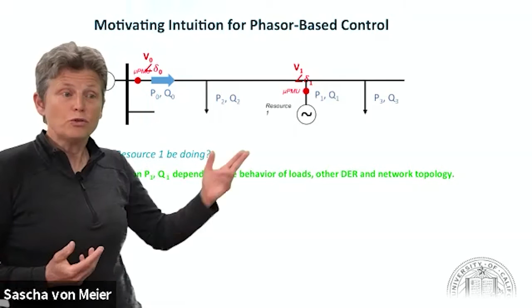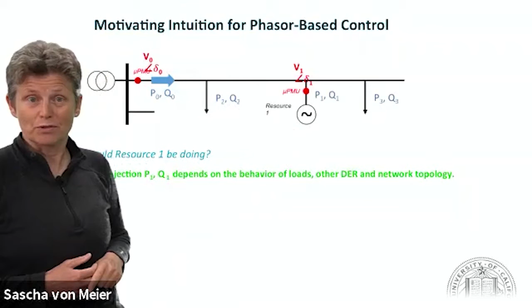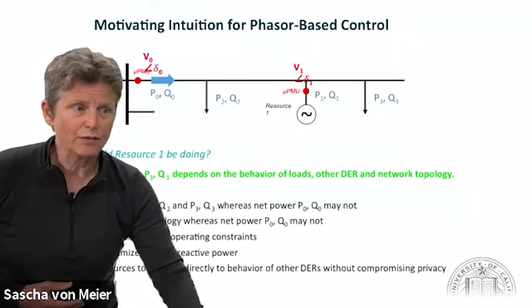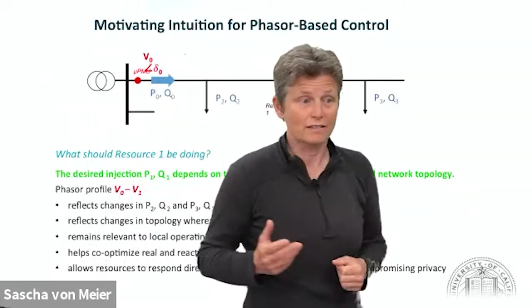But now there's a privacy issue: you can't actually observe directly what your neighbors are doing. You could measure the current at the feeder head and say, why don't we just hold that current constant? But by measuring the local phasor, we're getting more granular information about where that net power is coming from, and whether there's a lot of demand or overgeneration at the very end of the feeder that we might counteract, or whether it's closer to the top of the feeder where it doesn't make any difference.